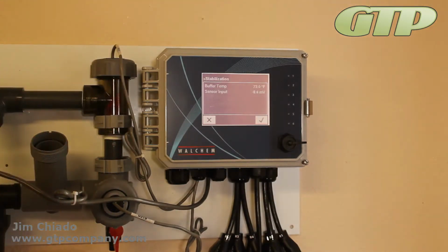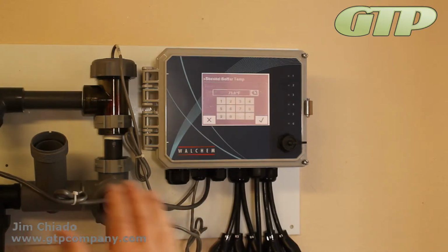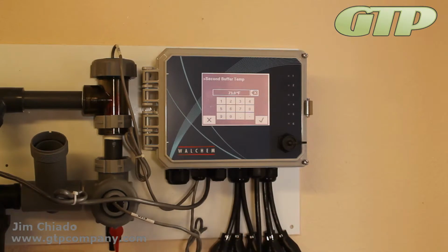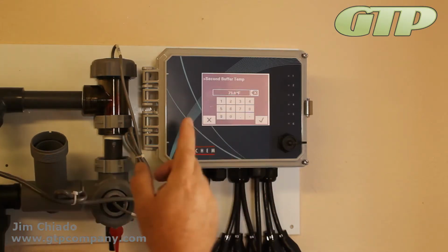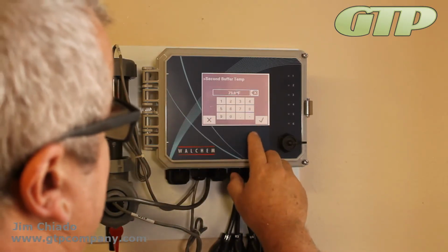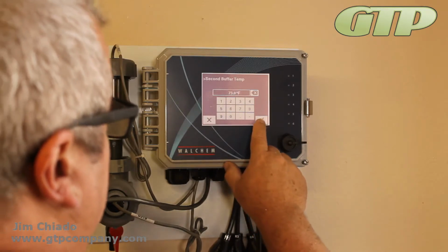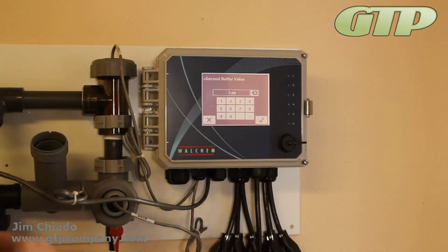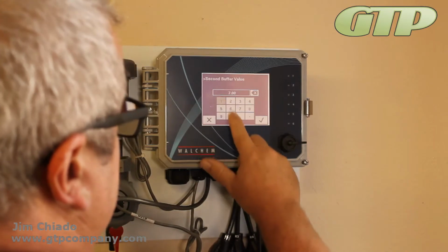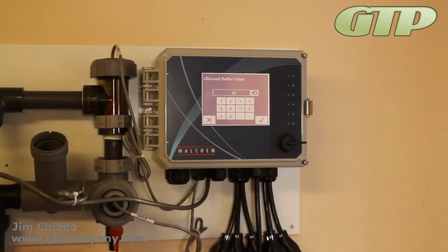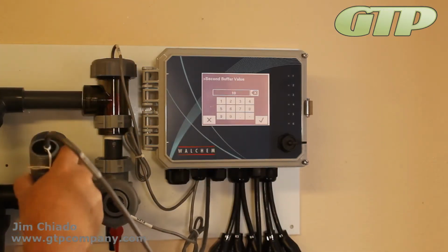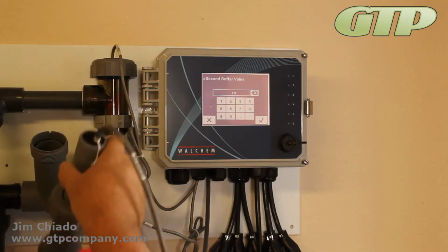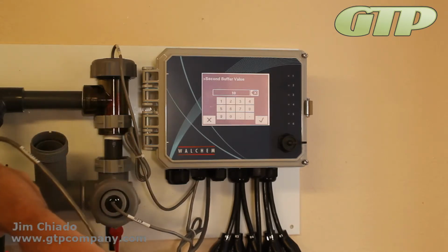When I do its auto calibration, I'm about -8 millivolts, so 7 really on a pH sensor is about 0. Okay, so that's why it was telling me that. It looks like it came back, it accepted that. So my second temperature buffer is still 73. I'm going to say okay. My second buffer though is 10. Am I telling it? Okay. Take it out, I'm going to rinse it a little bit, then I put it in the 10.